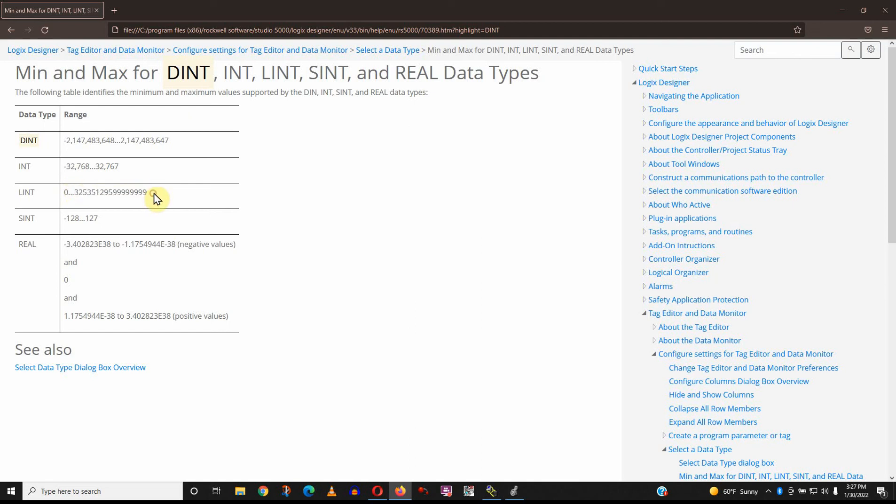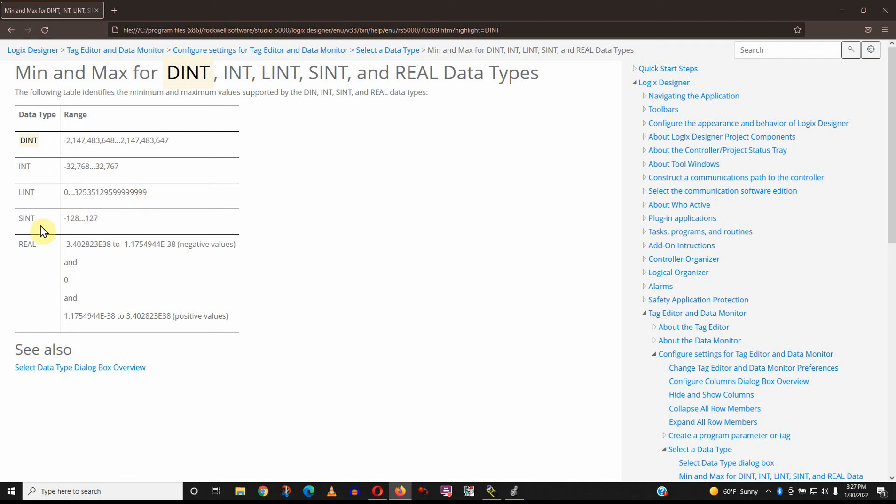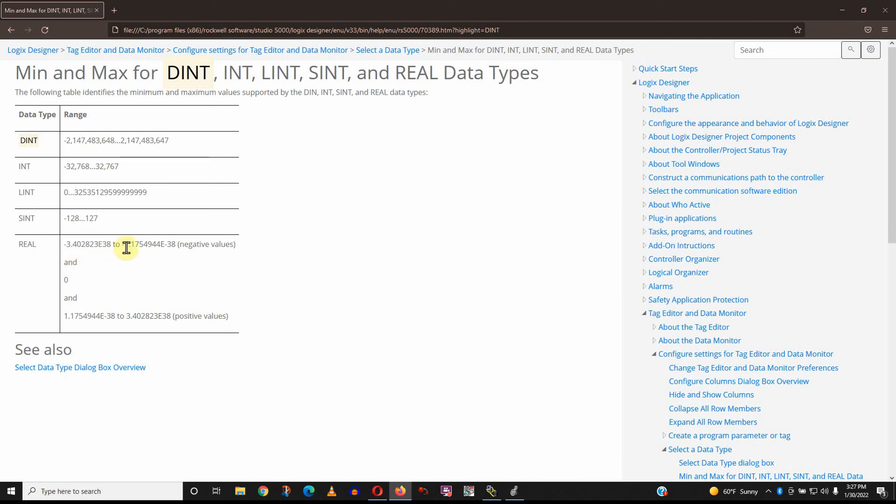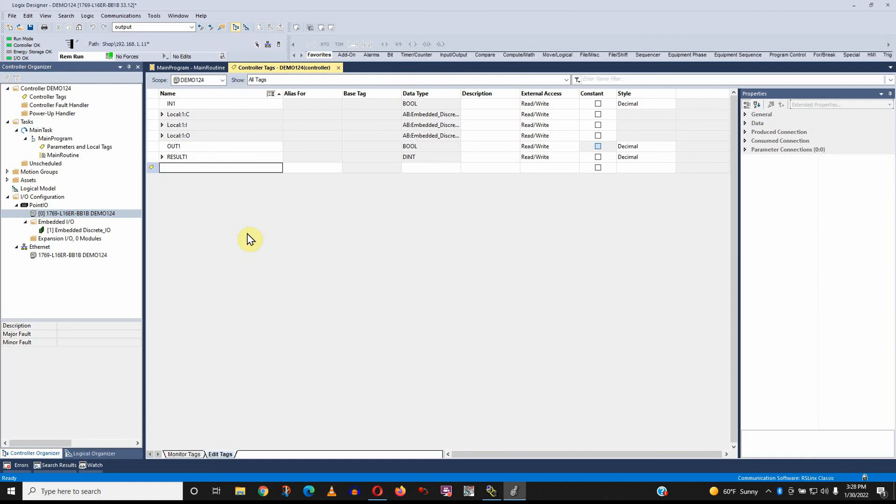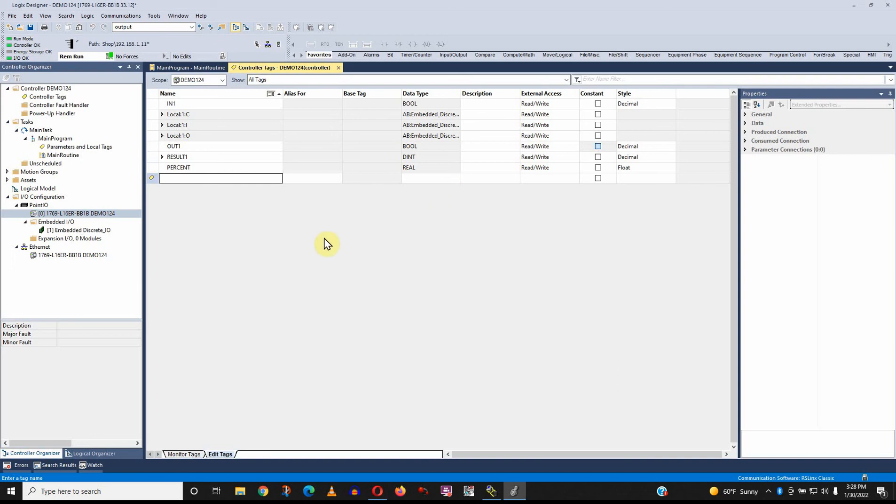Never used that. Just haven't had a use for it. It uses up more memory. It allocates more memory from the processor. So it's not really a big concern, but I wouldn't use long integers unless I just needed to use them. There's also a single integer, which is an 8-bit value, plus or minus 127, basically. There's a real number, which is like everyday numbers, 2.75 pounds. That's a real number. So if I need decimal precision, I have to use a real data type. So let's create a real data type. I'm going to call it percent. And before I press enter, I'm going to click on this and type the letters RE for real and press enter. That's known as a float, a floating point value.